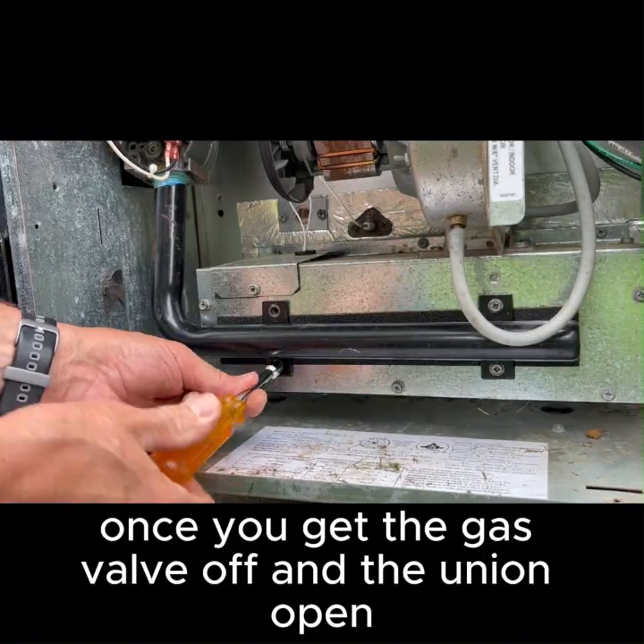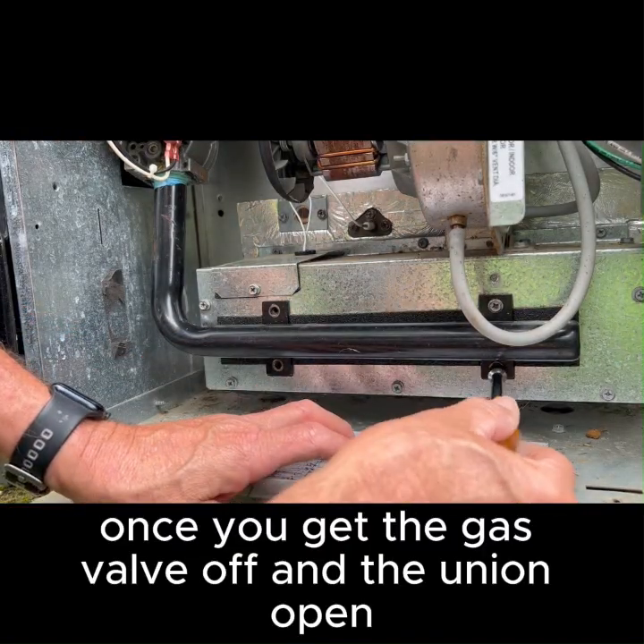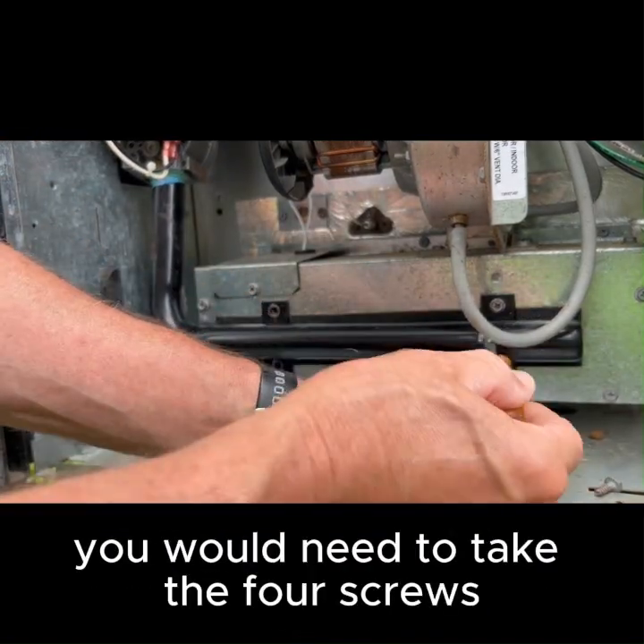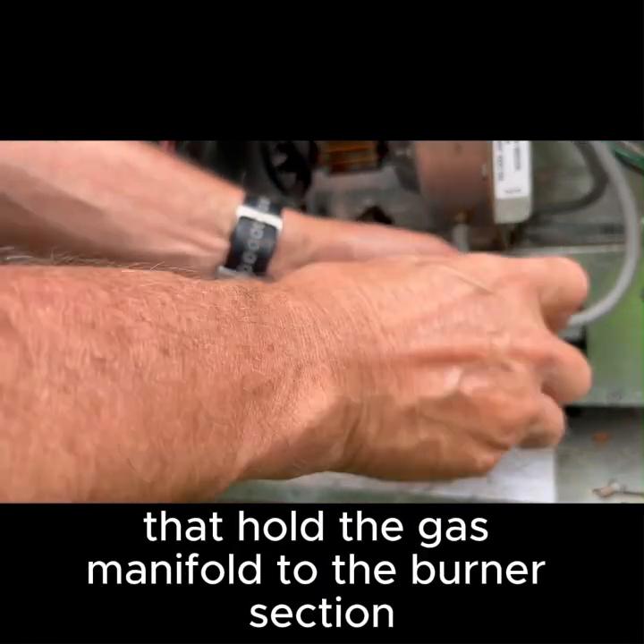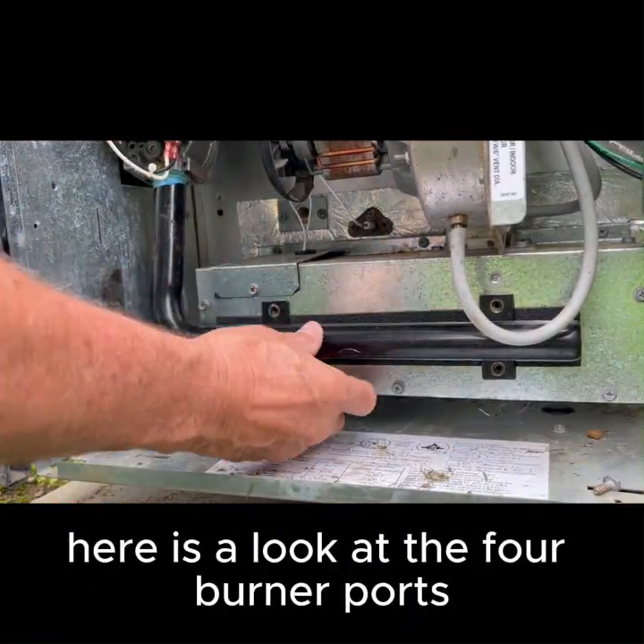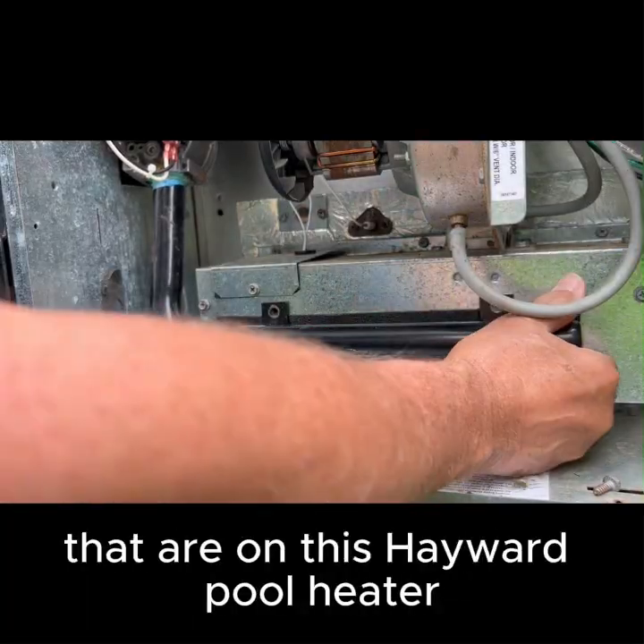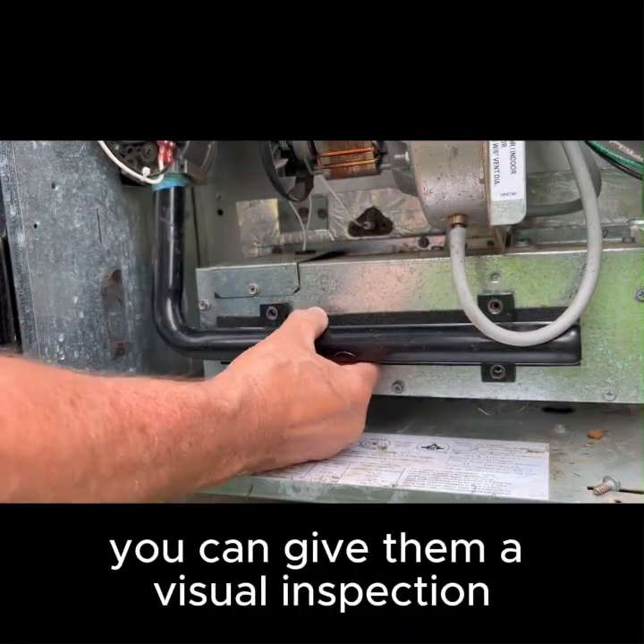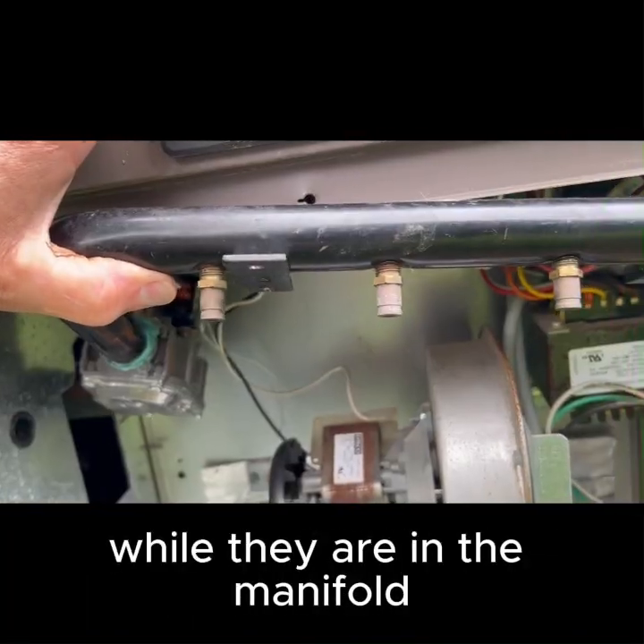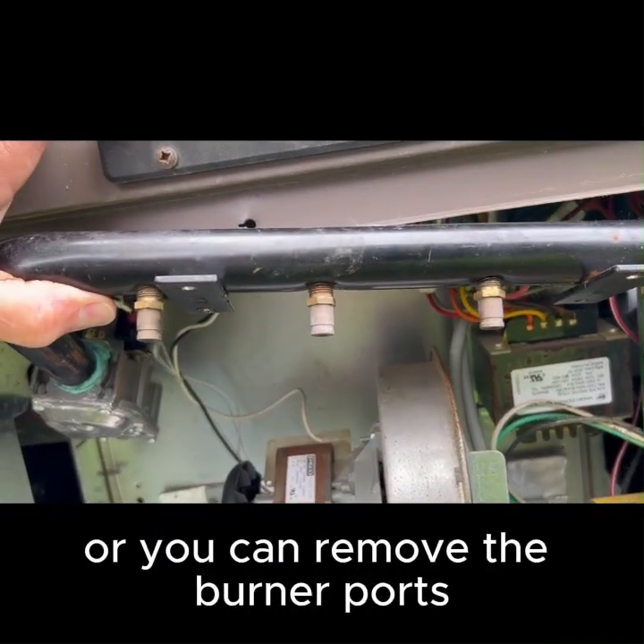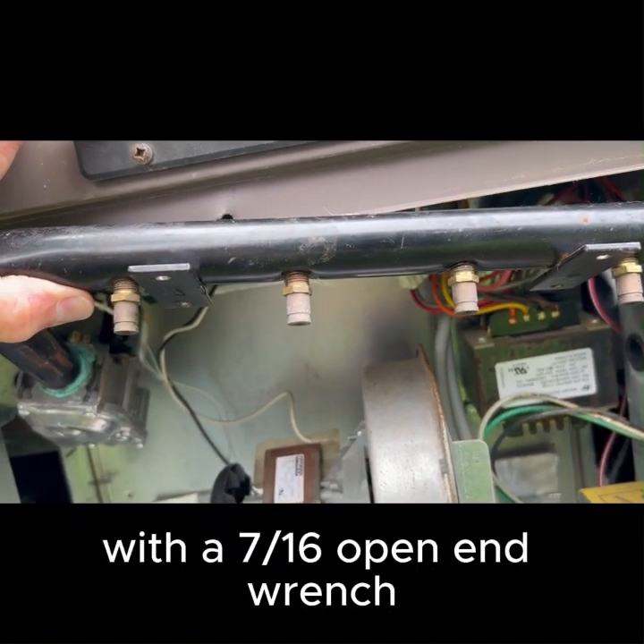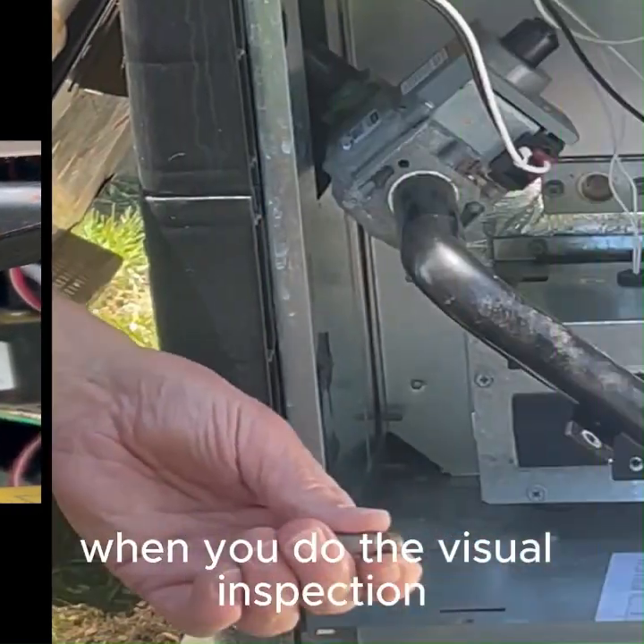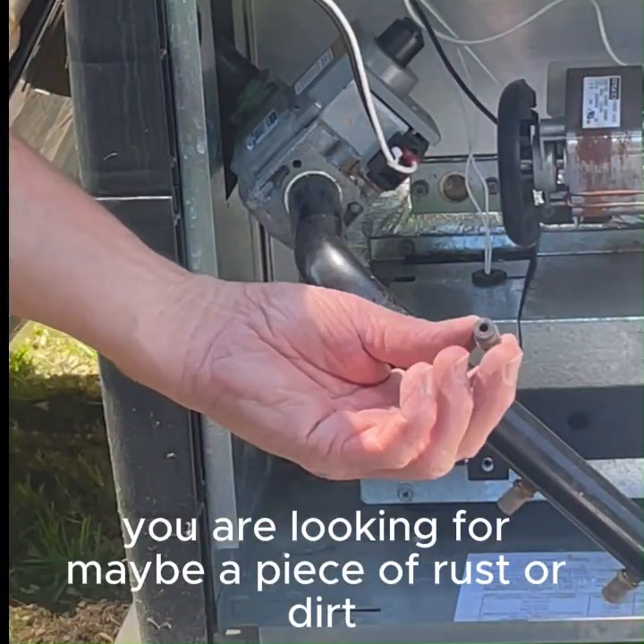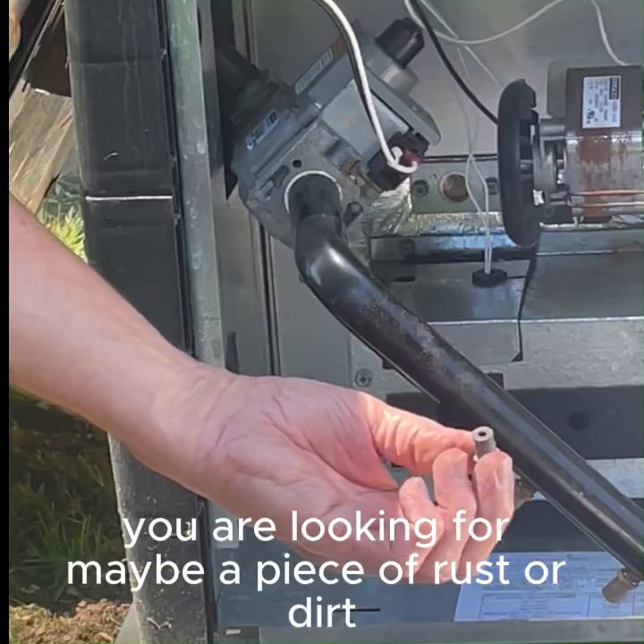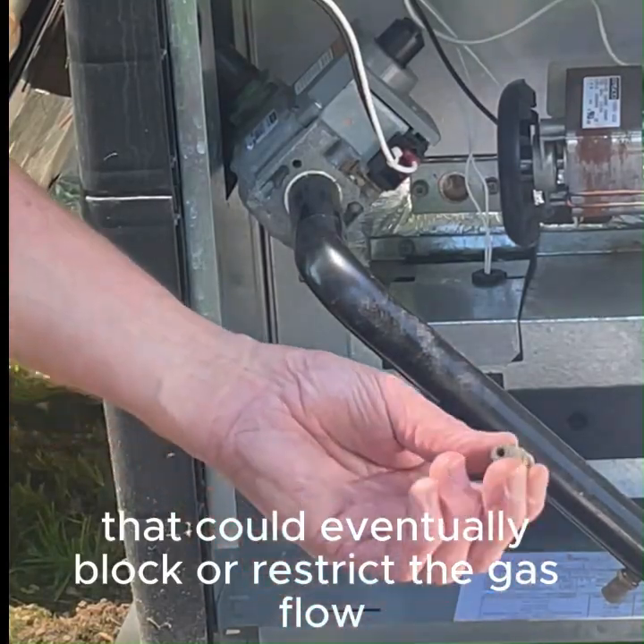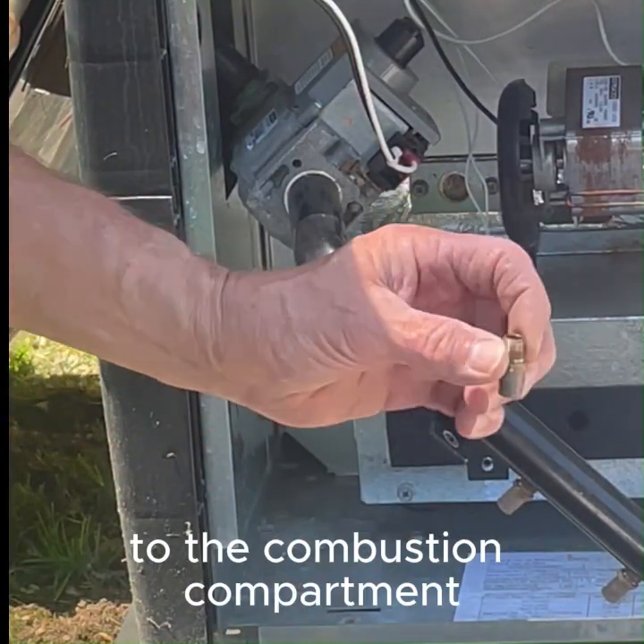Once you get the gas valve off and the union open, you would need to take the 4 screws that hold the gas manifold to the burner section. Here is a look at the 4 burner ports that are on this Hayward pool heater. You can give them a visual inspection while they are in the manifold, or you can remove the burner ports with a 7/16 open-end wrench. When you do the visual inspection, you are looking for maybe a piece of rust or dirt that could eventually block or restrict the gas flow to the combustion compartment.